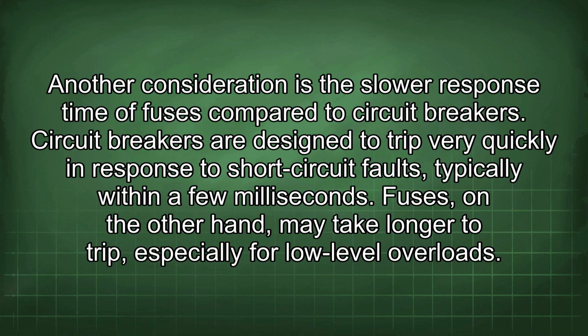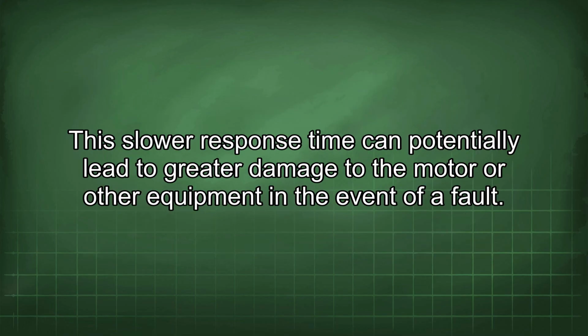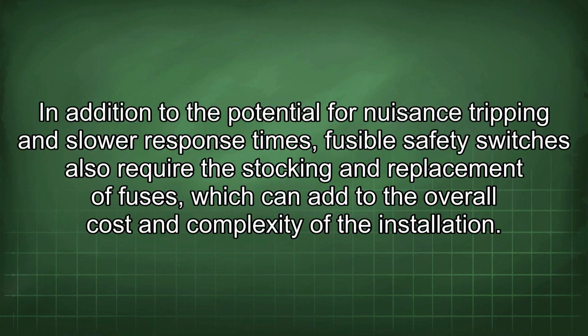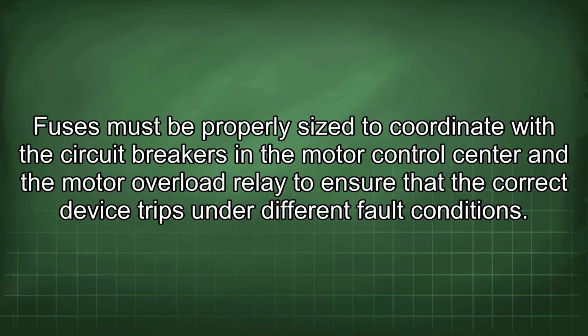Fuses, on the other hand, may take longer to trip, especially for low-level overload. This slower response time can potentially lead to greater damage to the motor or other equipment in the event of a fault. In addition to the potential for nuisance tripping and slower response times, fusible safety switches also require the stocking and replacement of fuses, which can add to the overall cost and complexity of the installation. Fuses must be properly sized to coordinate with the circuit breakers in the motor control center and the motor overload relay to ensure that the correct device trips under different fault conditions.